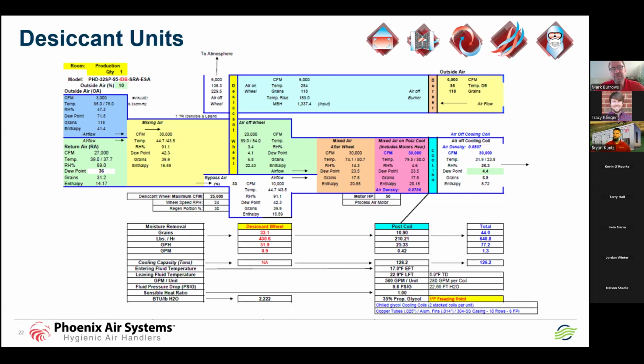Again, the desiccants certainly have their place, but in the harsh environments that we play in, you see what happens to these units where people don't change filters. What you definitely do not want is that desiccant wheel. This was a big deal, by the way, 15, 20 years ago in a lot of poultry plants. Every poultry plant that I've been to has a condensation problem. So what did they do? They would rent desiccant units. They proved their point. They work. They bought a big desiccant situation. And then the plant guy is like, how do I clean this? How do I replace the wheel?